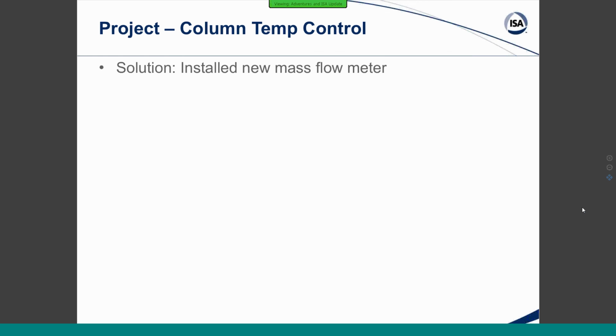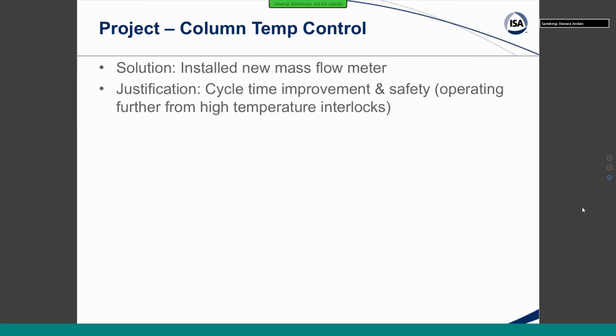So we needed to install a new flow meter, and we were able to justify this on two different things. The first one, again going to dollar values, is a cycle time improvement, and in this case, it was increased production. We also had a safety justification here because we were going to be making this operate further away from that high temperature interlock. We wouldn't be putting the batches into held so often.